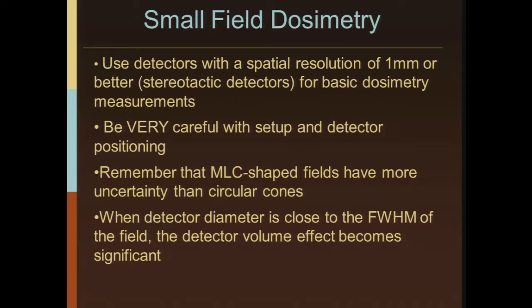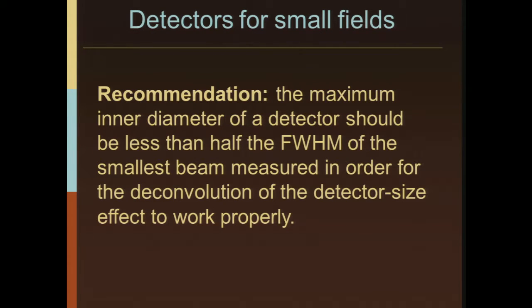When detector diameter is close to the full width half maximum of the field, the detector volume effect becomes very significant. Several people asked me about this, so I wanted to include a recommendation in the slides: the maximum inner diameter of a detector should be less than half the full width half maximum of the smallest beam measured, in order for the deconvolution of the detector size effect to work properly. That's a good one to keep in mind, and you could discuss that in the discussion groups.